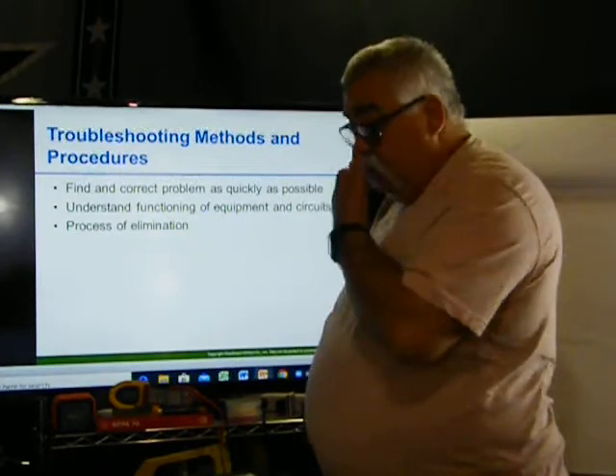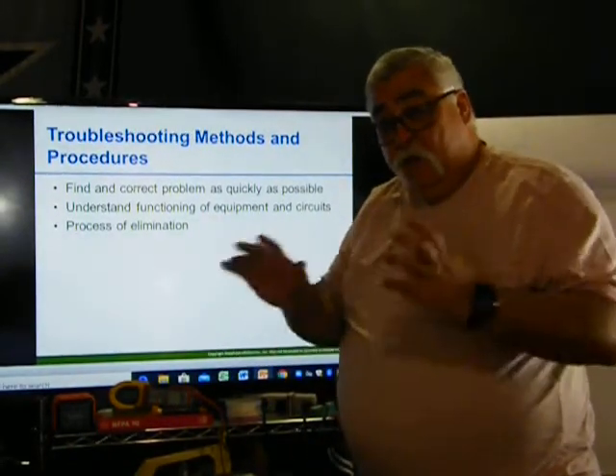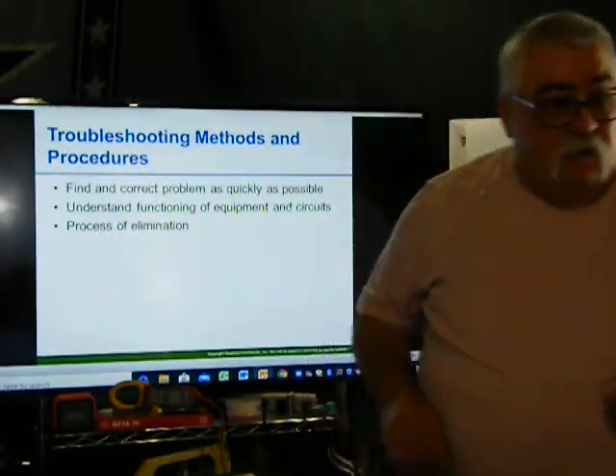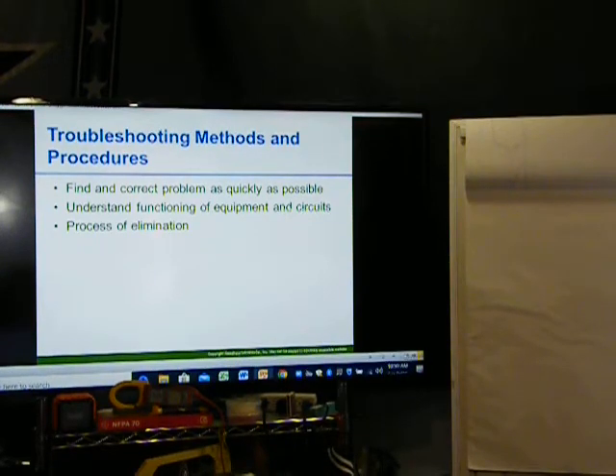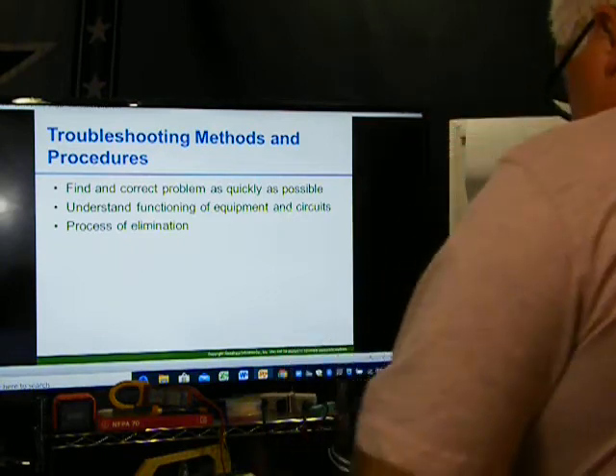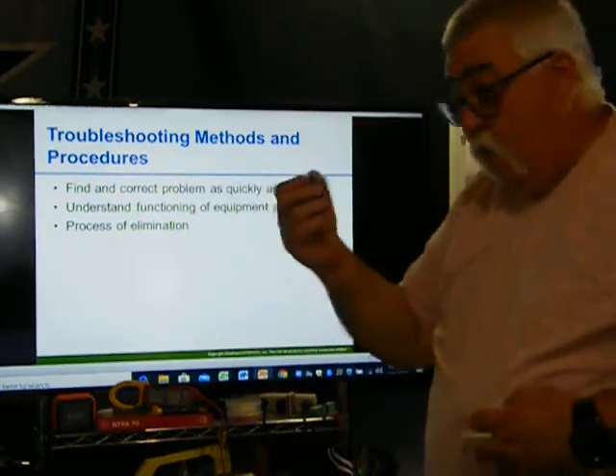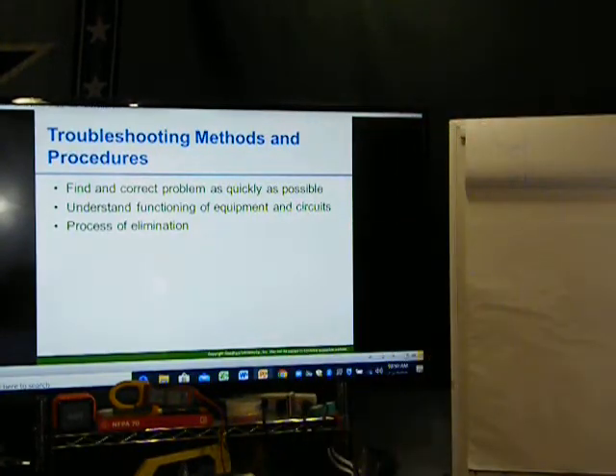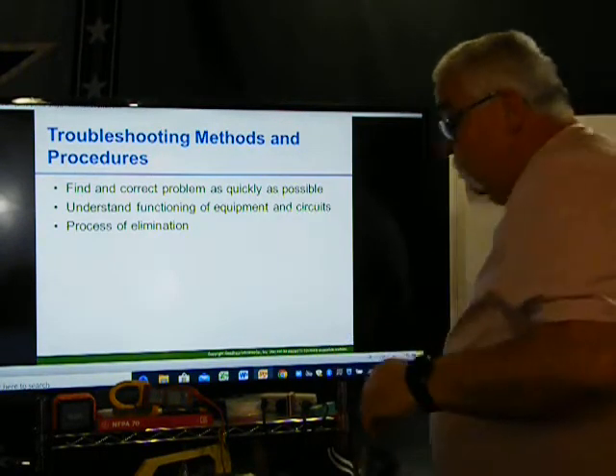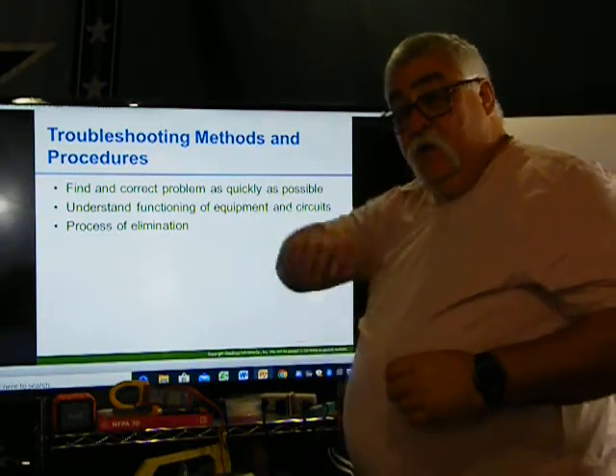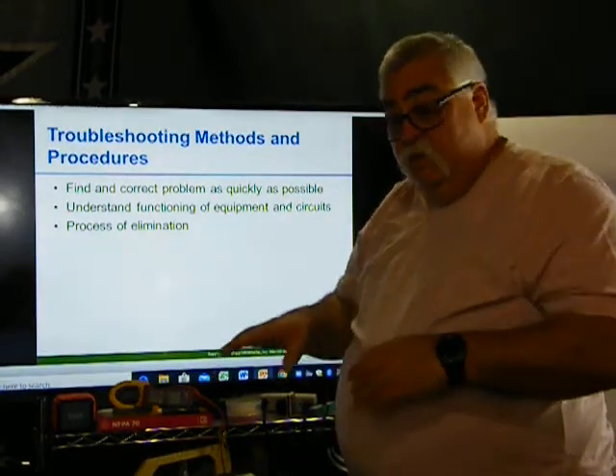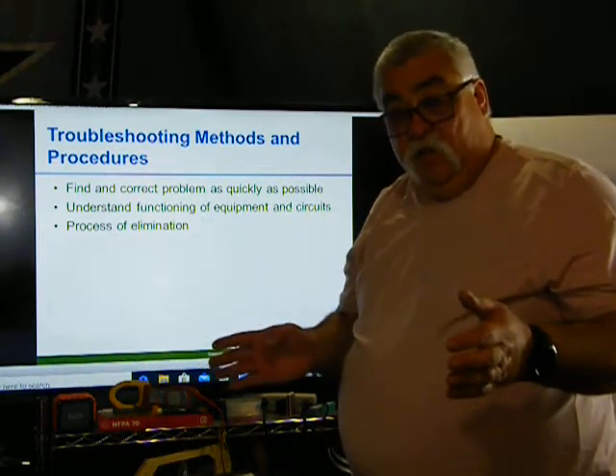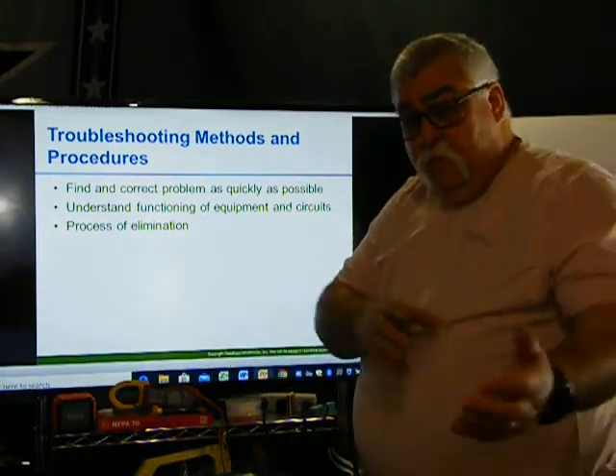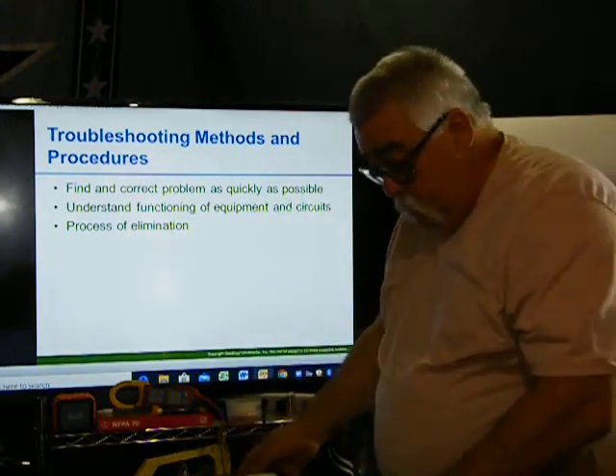Sometimes you may have to find a schematic because you don't know how it's wired, so you have to bring out a schematic. You may have small relays here and there. I'll talk about small relays, the ice cube ones. These can go bad. Contactors, I'll get those later. But take a timer relay: guess what, that timer goes bad. Let's say it goes into motion, and when it goes from step 1 to step 2, it has a 10-second or 30-second delay. Well, it does step 1, but it doesn't go to step 2. Why? Maybe that timer's not going. We'll get into that later.